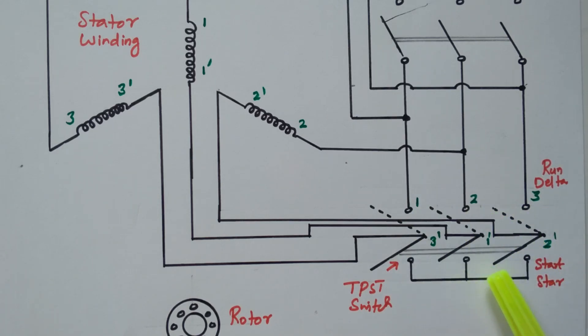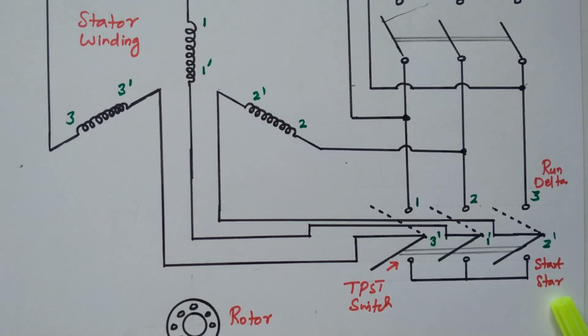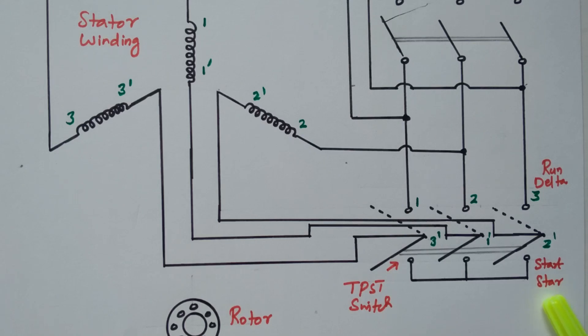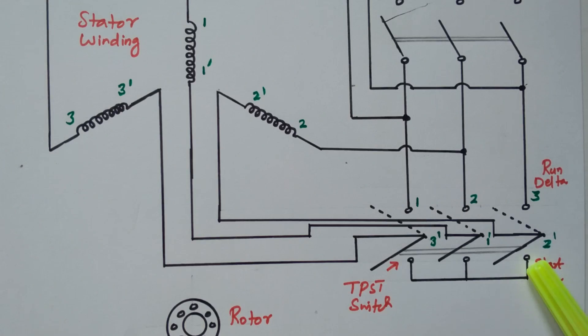During starting, the TPST switch is placed in the star connection. Why are we connecting star connection? In the star connection, the voltage is reduced by the factor 1 by root 3. The nature of the star connection is that only 1 by root 3 of the voltage will be applied to the stator winding. So due to this reduced voltage, the current drawn by the stator also reduces. Once the induction motor gains normal speed, the switch is changed over to the running condition — that is the delta connection.